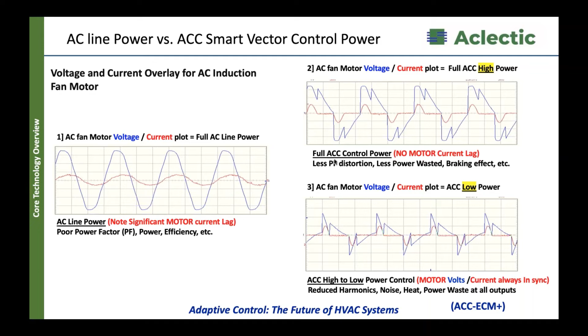Some other features the box has is a soft start. Won't get into it, but the idea is just quickly, when you think of a PSC motor, it's a big hunk of copper until you get it moving. And so when you plug it in, you may see the lights dim because it's a short. It's literally a dead short when it's first turned on. And that's why you get that surge, an inrush. And that's why they have staggered on time.